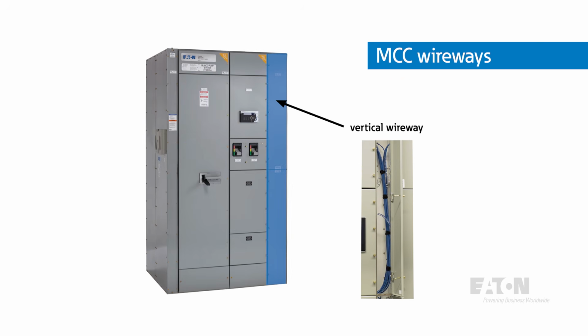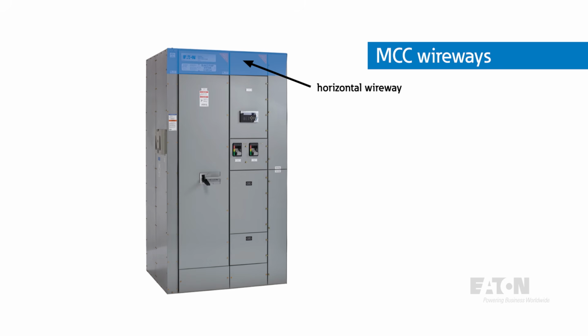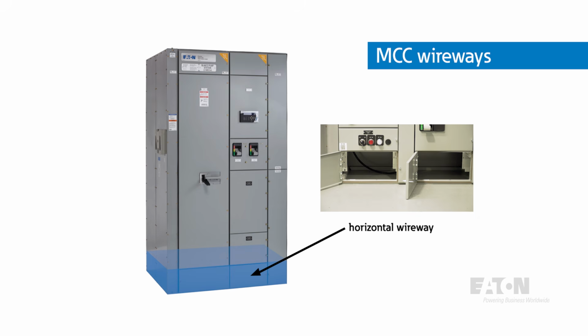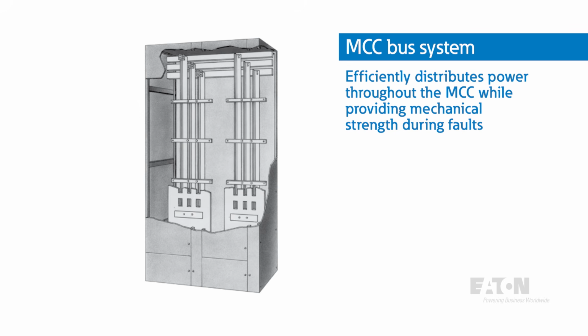Each structure includes a vertical wireway on the right side that extends along the full height to accommodate wiring. The top front horizontal wireway spans the full width of each structure and is isolated from the main horizontal bus. The bottom horizontal wireway extends the full depth of the structure, allowing for unrestricted conduit entry. The bus system efficiently distributes power throughout the MCC and provides mechanical strength during faults.